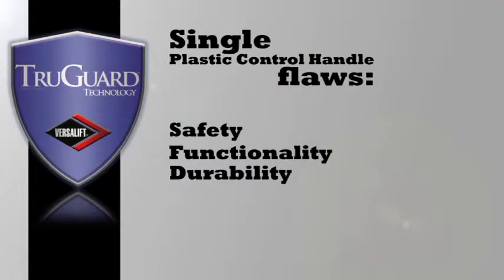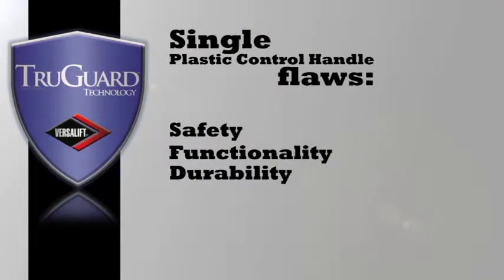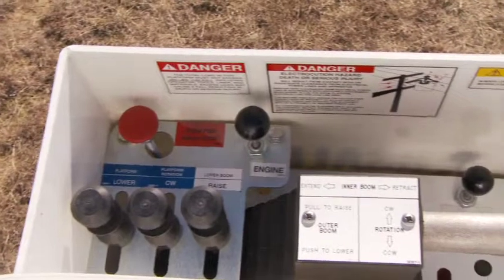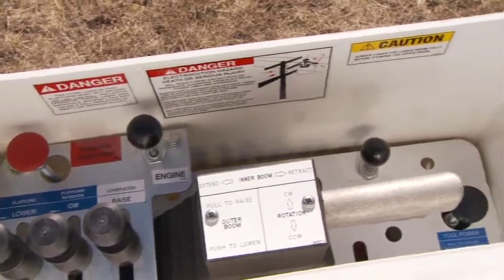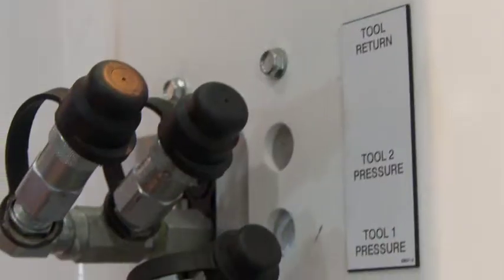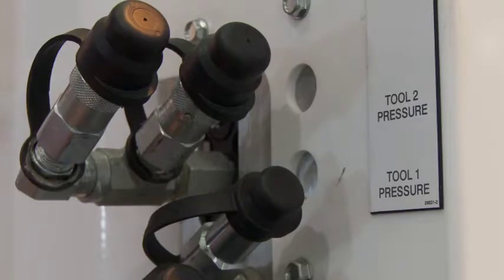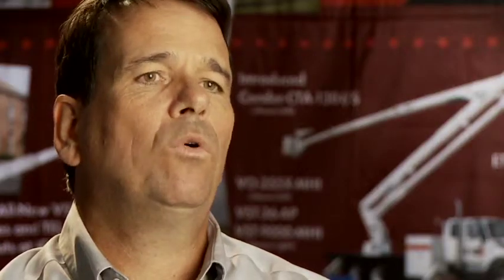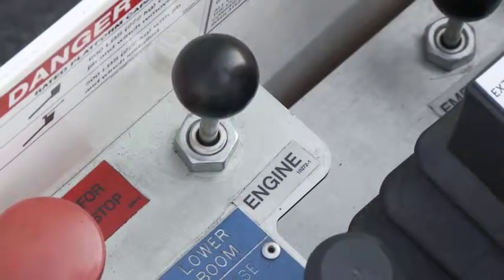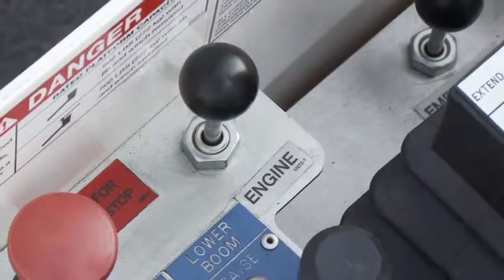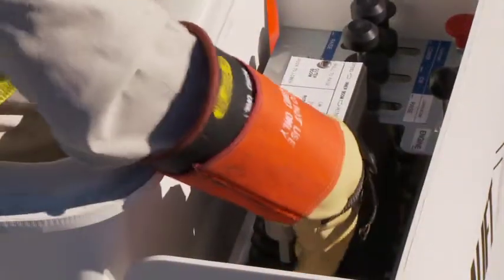The single-handle plastic design offers limited protection as it only protects one handle. If you'll notice at the upper controls, there's multiple handles that the operator can come in contact with. And not only the controls, we're also concerned with the tool port connections that he hooks his hydraulic tools to. This can be an issue if they become energized also. In addition to the controls and tool ports, there's also concern with the control panel top, and this can also be another contact area for the operator.